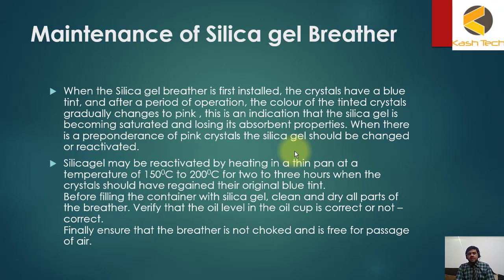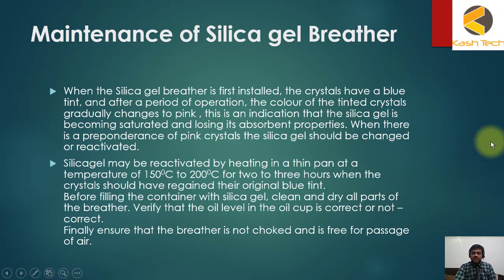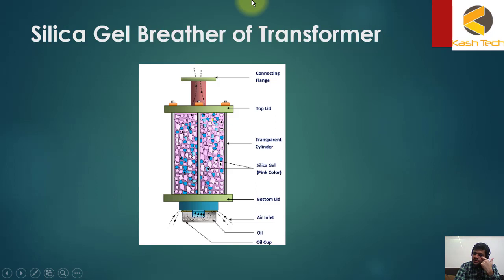There are two options: either replace the silica gel or regenerate it by heating up to 200 degrees centigrade for two to three hours to dry it out. Also check that air is passing through properly, check the oil level, and change the oil if needed. As shown in this picture, the color has changed from blue to pink, meaning it is time to take action.